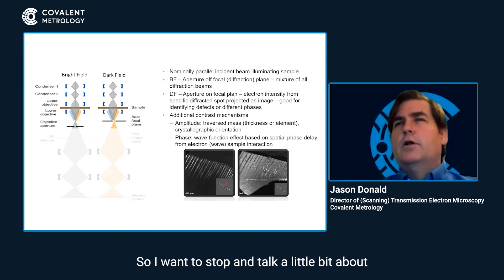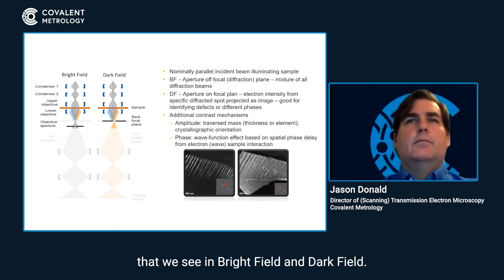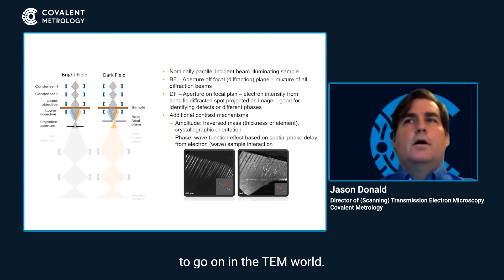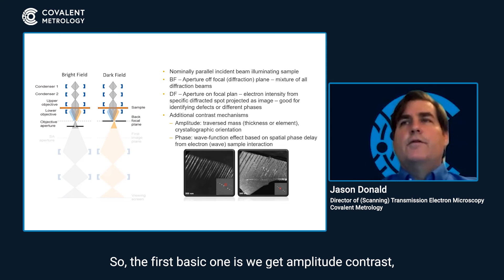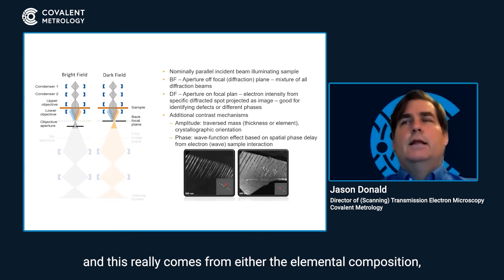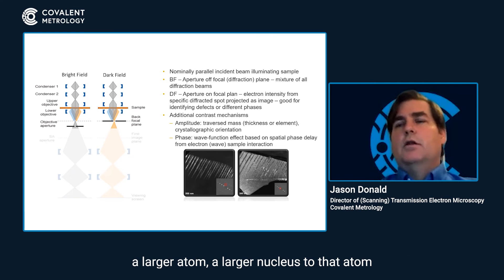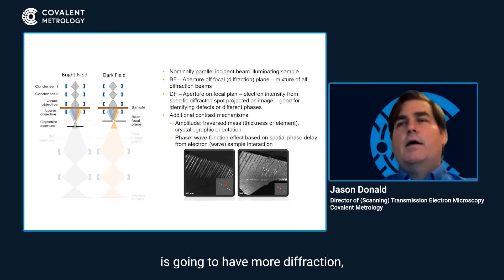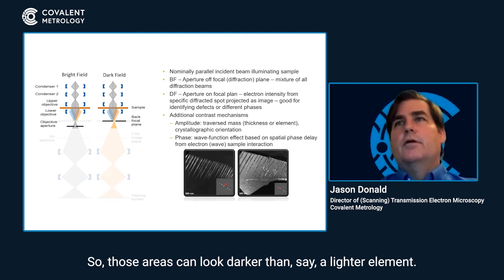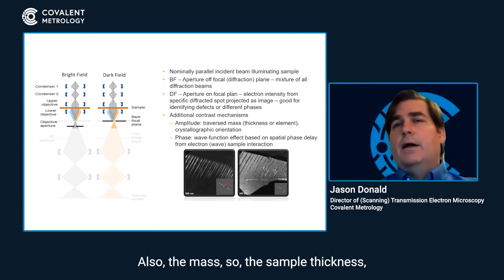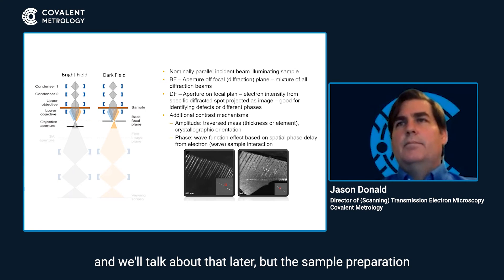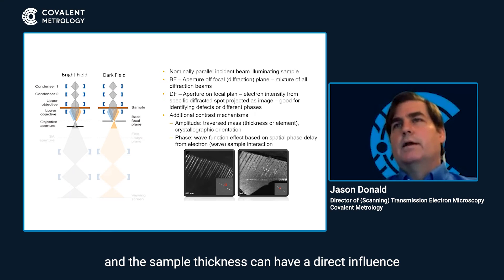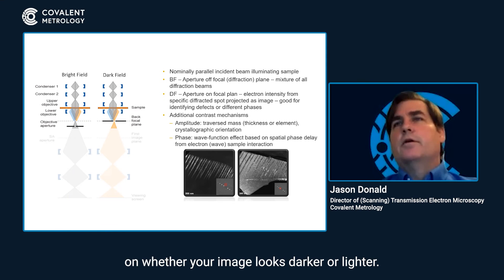I want to talk a little about the contrast mechanisms we see in bright field and dark field, because there are some interesting things that go on in the TEM world. The first basic one is amplitude contrast, which comes from either the elemental composition — a larger atom with a larger nucleus is going to have more diffraction and scatter the beam in a greater amount, so those areas can look darker than a lighter element. Also the mass and sample thickness can have a direct influence on whether your image looks darker or lighter.